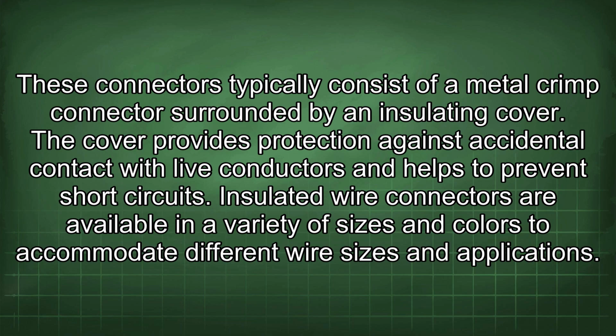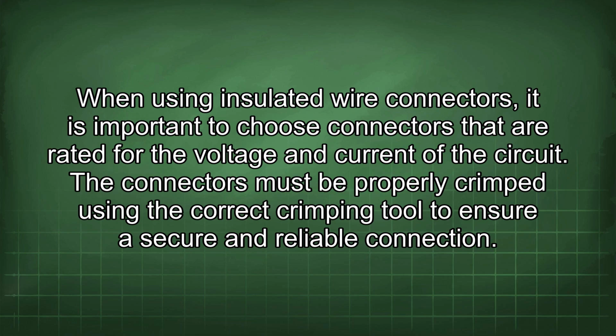These connectors typically consist of a metal crimp connector surrounded by an insulating cover. The cover provides protection against accidental contact with live conductors and helps to prevent short circuits. Insulated wire connectors are available in a variety of sizes and colors to accommodate different wire sizes and applications. When using insulated wire connectors, it is important to choose connectors that are rated for the voltage and current of the circuit. The connectors must be properly crimped using the correct crimping tool to ensure a secure and reliable connection.